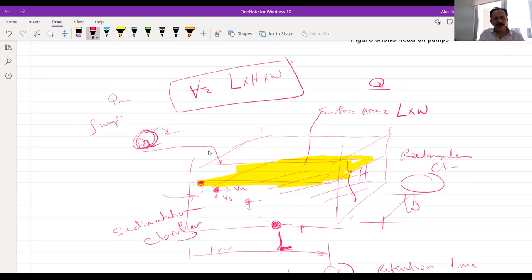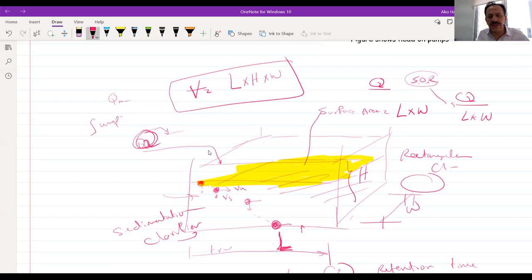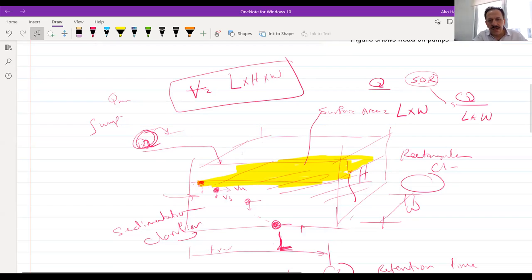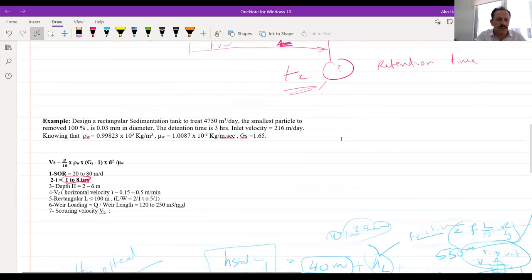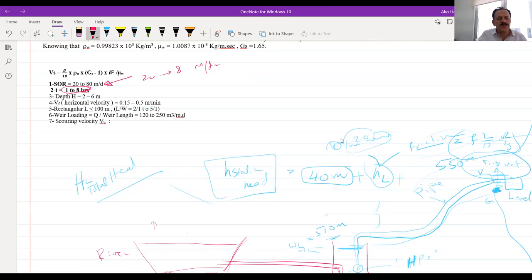Q divided by the surface area (length × width) gives a term called SOR — surface overflow rate. SOR is a very important design parameter. It should be between 20 to 80 meters per day, meaning one square meter of tank area can treat 20 to 80 cubic meters per day under normal conditions.